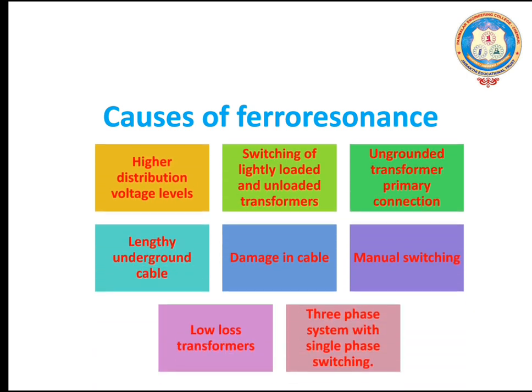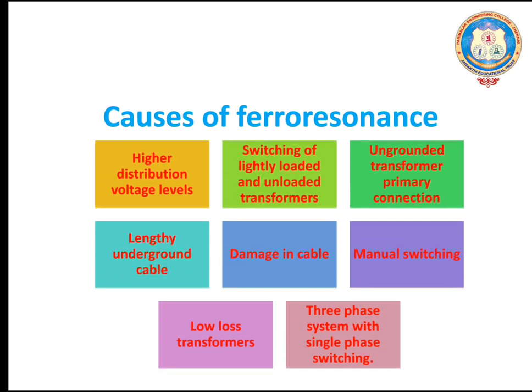What are the causes of ferro-resonance? Higher distribution voltage levels, switching of the lightly loaded and unloaded transformers, ungrounded transformer primary connection, lengthy underground cable, damaging cables, manual switching, low-loss transformer, and three-phase system with single-phase switching.